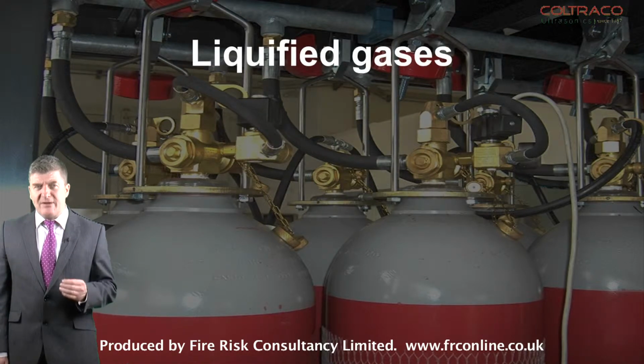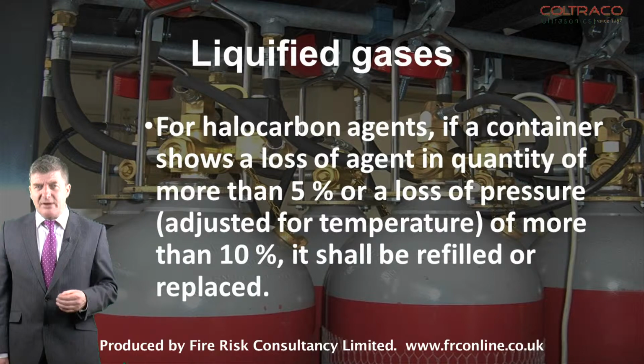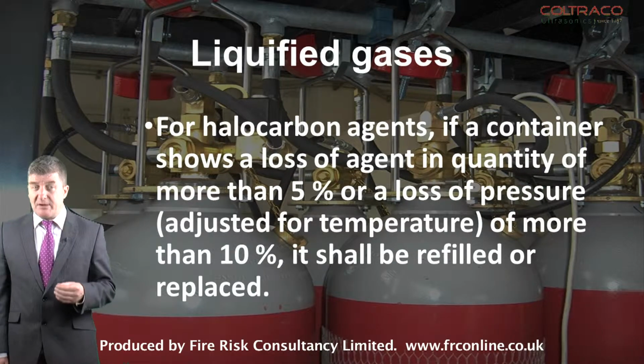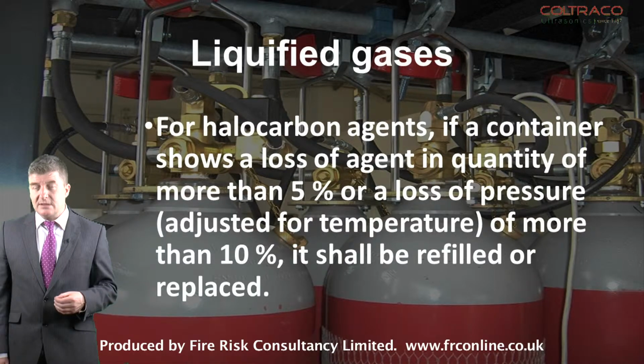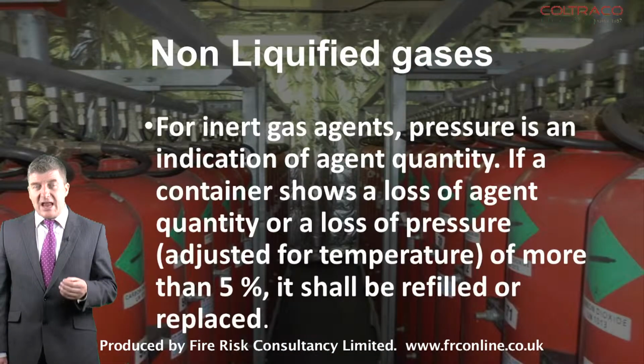Now, first of all, liquefied gases. For the halocarbon agents, if a container shows a loss of agent of more than 5% or a loss of pressure of more than 10%, it shall be refilled or replaced. Non-liquefied gases. For inert gas agents, pressure is an indication of agent quantity. If a container shows a loss of agent quantity or a loss of pressure, this can be adjusted for the temperature, of more than 5%, it shall be refilled or replaced.